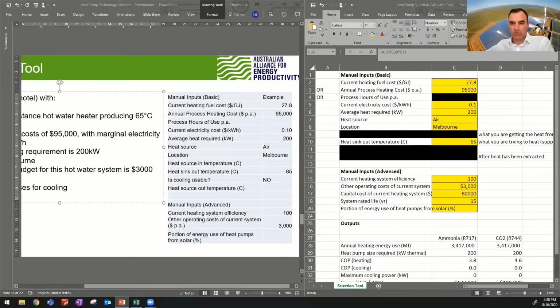And while commercialised elsewhere, we may say not commercialised in Australia. So there's the other refrigerants, the R1234 with the letters afterwards, that we could incorporate into this fairly easily. We took a cautious approach considering there's some uncertainty about those refrigerants being available in 10 years' time. But if that changes, I'm sure we can easily update it to add those refrigerants as well. And certainly if we start looking above 100 degrees with this tool, we'd need to include the R1234s as well.